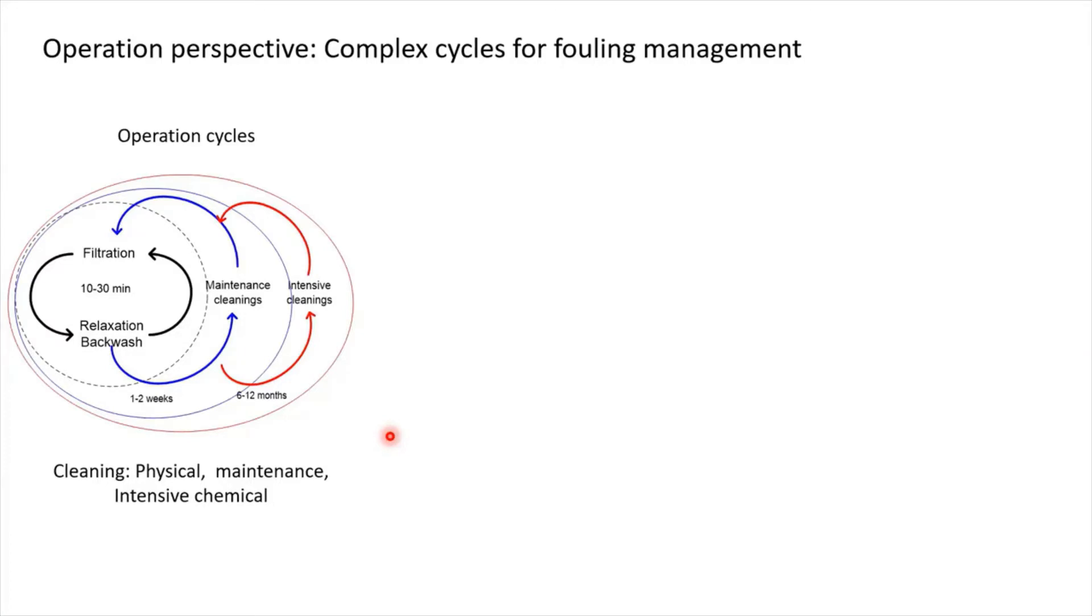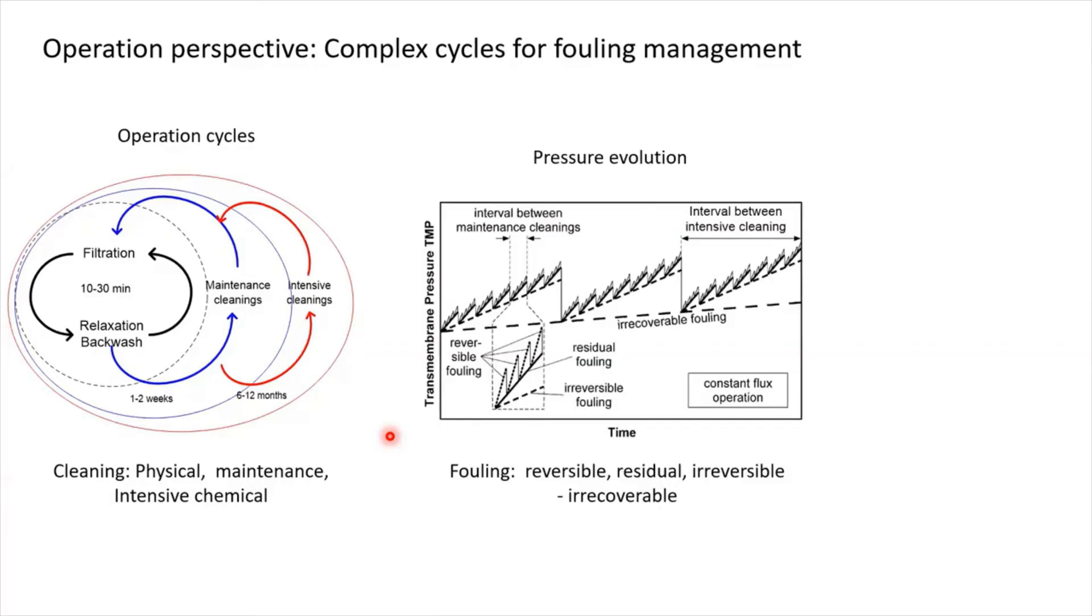So the operation is complex. If you want to portray the complexity of operation in the pressure evolution, as you can see here, you see the transmembrane pressure goes up over time, you do the cleaning, go up, cleaning, go up, cleaning and so on. As a function of time, because of the permanent fouling, you will lose the original performance of the membrane and eventually need to replace the membrane.